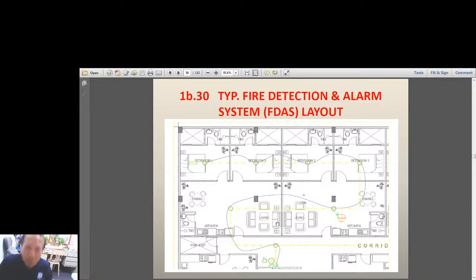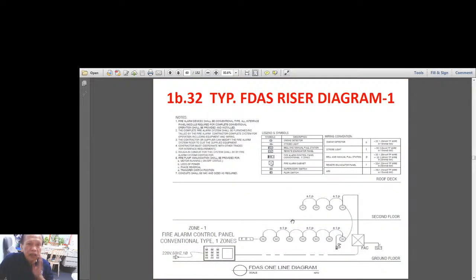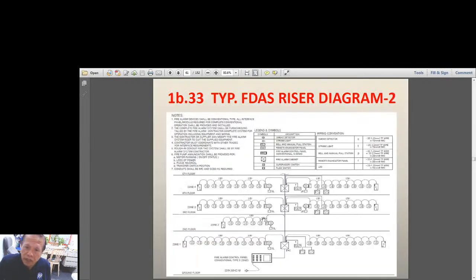Okay, so that's the usual plan, and to show the vertical riser, you would show it like this, a one-line diagram. These circles are the smoke detectors on the second floor, and here are the smoke detectors on the ground floor. And the fire alarm cabinet here, and here you have a remote annunciator panel, and of course the buzzer, and here is the fire alarm control panel. So that's for a two-story building. For a higher building, you would show it like this.